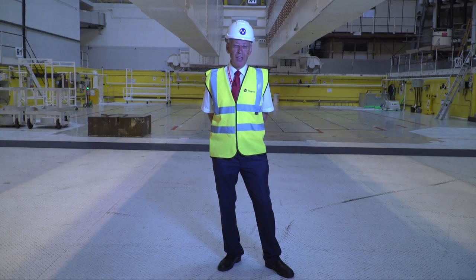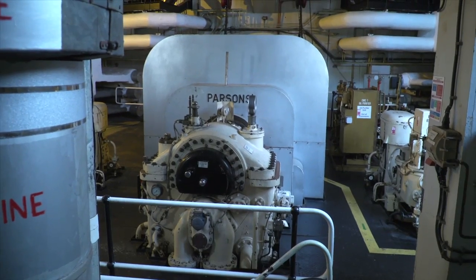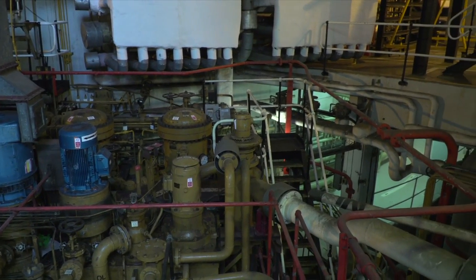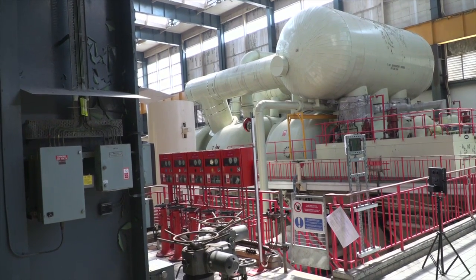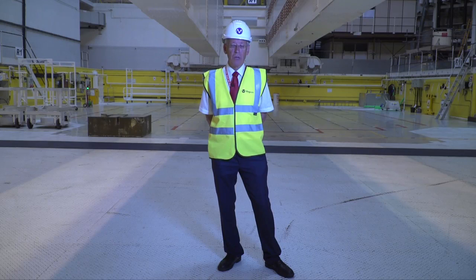The gas is circulated round. The gas is at quite a high pressure, and it's circulated round inside the core by some large steam-driven gas circulators, which are elsewhere down in the reactor hall, well below us. There are some pipes which bring feed water into the boilers. That's turned into steam by the heat in the reactor, and the steam then goes off and turns the steam turbine generators to generate electricity. This type of reactor, the Magnox reactor, is one of the very few in the world that's able to change the fuel while the reactor's at power — on-load refueling, we called it.